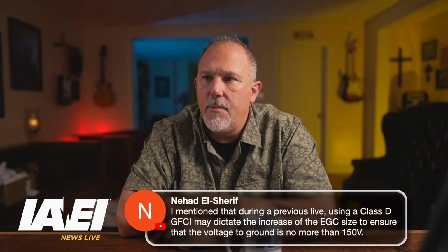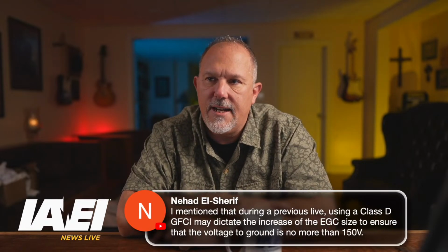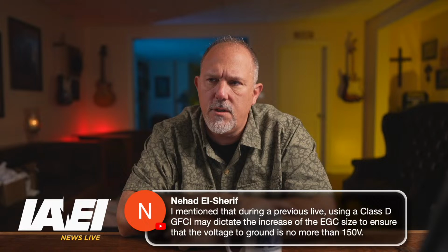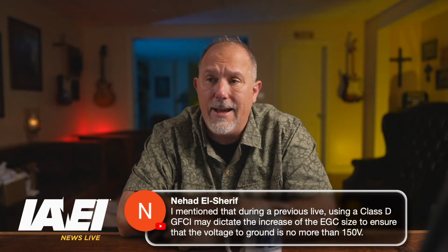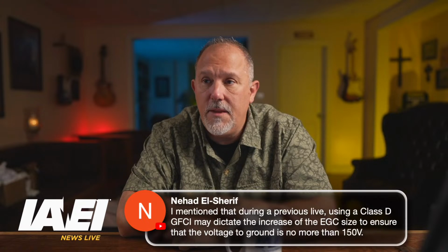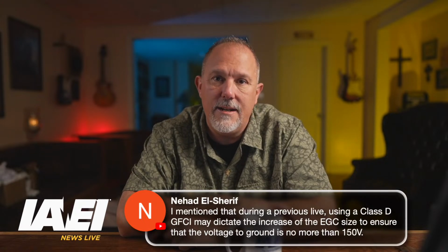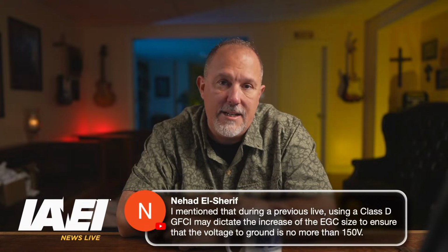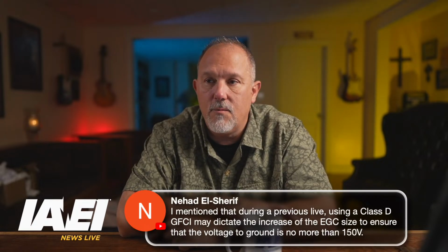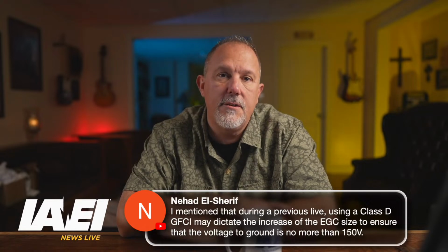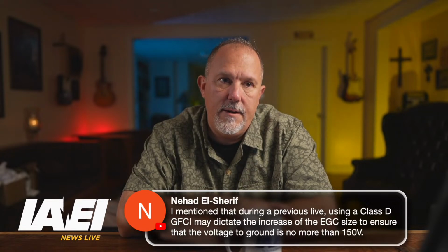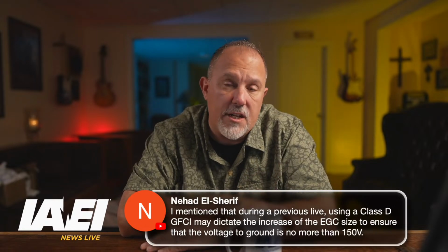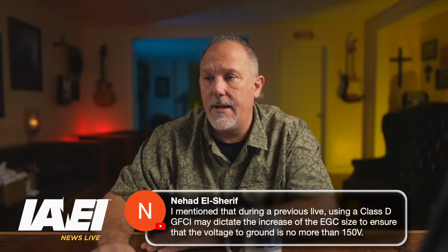Okay, so let's go back. Nihad mentioned that during a previous live, using a Class D GFCI may dictate the increase of an equipment grounding conductor size to ensure that the voltage to ground is not more than... yeah. So which is a completely different... So if you're applying a Class D special purpose GFCI, yeah, you have to really look at the size of the equipment grounding conductor, absolutely. But if I'm doing just ground fault protection of equipment, I don't need to worry about that.